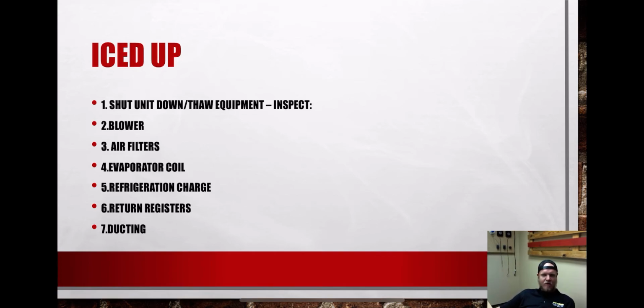But inspecting everything, don't give anybody a call. Don't call and ask for help with trying to diagnose the equipment if you have not thawed out the equipment. We cannot help in any sort of way if the equipment isn't 100% thawed out, because none of your numbers matter. Your amperage doesn't matter, your temperatures, your pressures, none of that matters at all unless every piece of ice is off that piece of equipment. Everything here is just what you're going to inspect while you're thawing it down, or right after it's already thawed out.